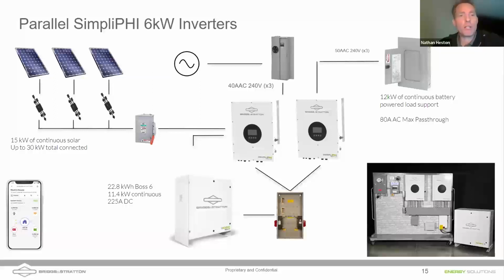And so what I'm showing here is just a simple single line diagram for what critical load backup would look like. This is a partial home backup. We're not backing everything up. Our inverters are parallel. We can put up to 4 of these units in parallel to get more power output. You're looking at rapid shutdown devices there on the left on the solar panels, a disconnect, of course, and then a fused disconnect on the bottom for the batteries.